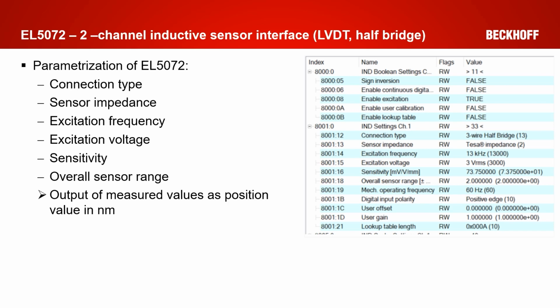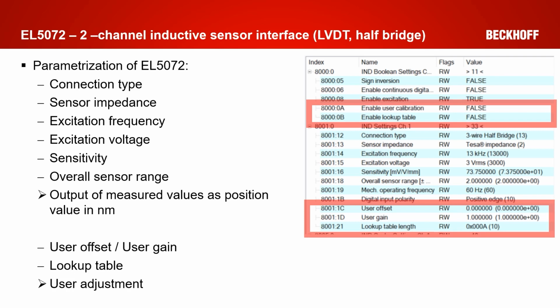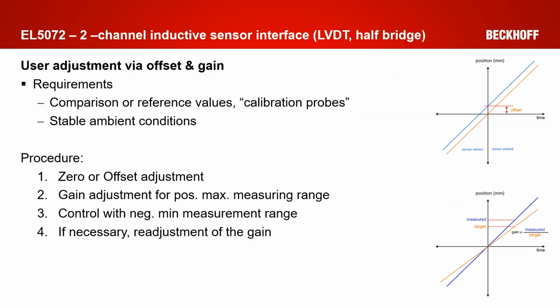Therefore, we have created two possibilities to do a user adjustment. On the one hand, it's our offset and user gain parameters, and on the other hand, it's a lookup table with up to 20 entries. Let's have a look at a simple adjustment that can be carried out via the offset and user gain. The requirements for user adjustment are some comparison or reference values. Furthermore, for some half bridges, so-called calibration probes are also available from the manufacturer.